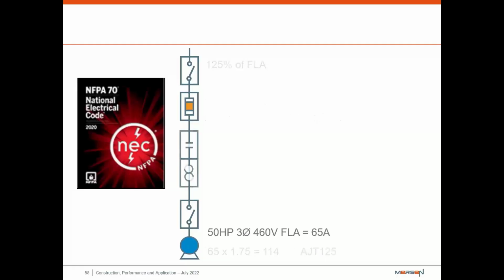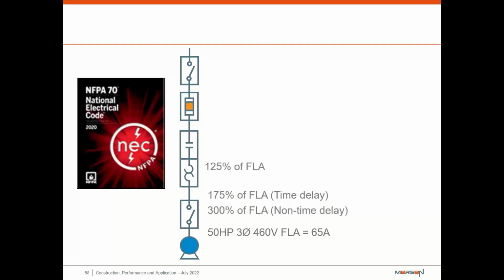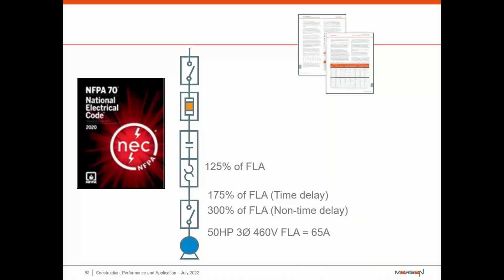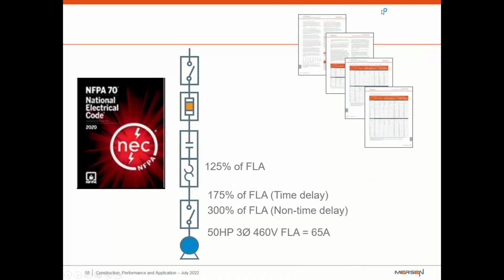Sticking with the same numbers here, you're allowed to have 125% if it's going to provide the overload protection and the short circuit current protection. But if you're going to be using a time delayed fuse, you want to do 175%. If it's going to be non-time delayed, it's going to be 300%. So let's take a look at some of those numbers. Also, this is all going to be in our advisor, and it's also available online. So if you have any questions on this, you're not going to have to do any of the math yourself, and we're always available to help you as well.